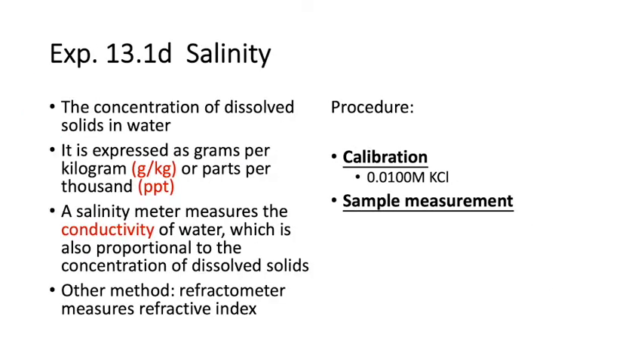Now let's move to the salinity measurement. The salinity means the concentration of the dissolved solid in water. Salinity can be expressed as gram per kilogram, g per kg, or part per thousand. A salinity meter measures the conductivity of the water, which is proportional to the concentration of the dissolved solid. There are other methods for measuring the salinity. For example, use the refractometer to measure the refractive index of a series of sodium chloride standard solutions.